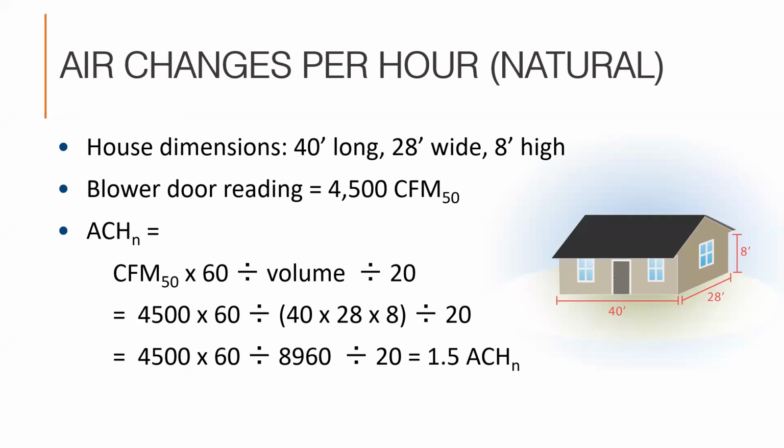Well, that's a super leaky house. In fact, it's 4 times leakier than the 0.35 target that PG&E is looking for, which means there is a ton of opportunity for improved comfort and reduced energy bills by performing air sealing at that house.